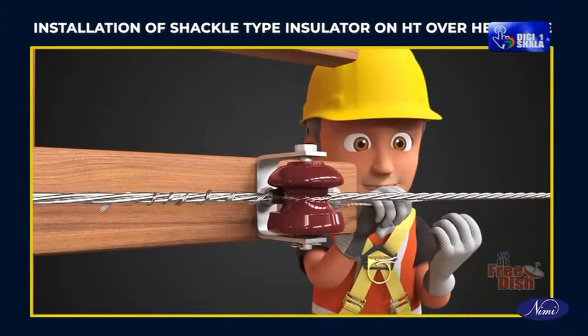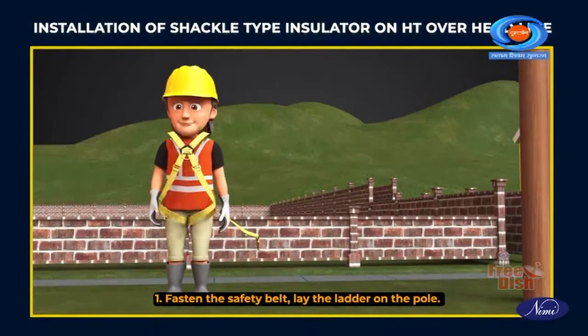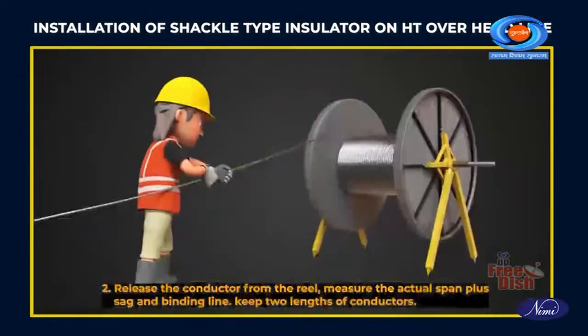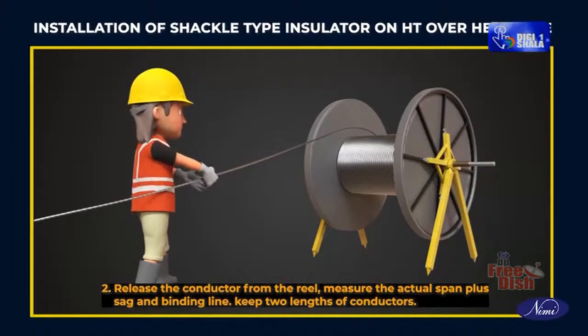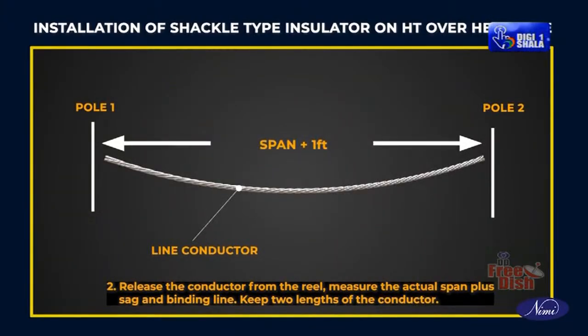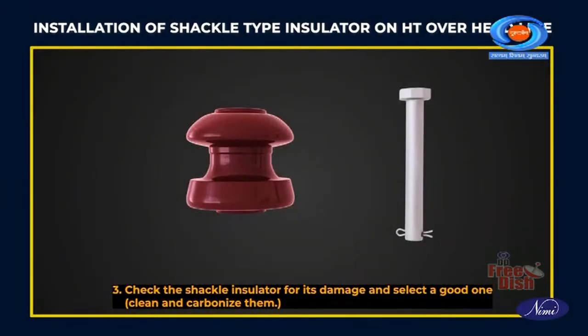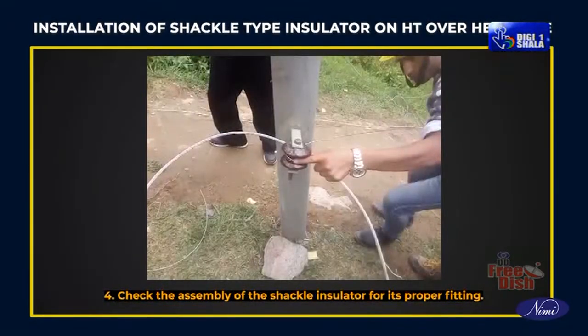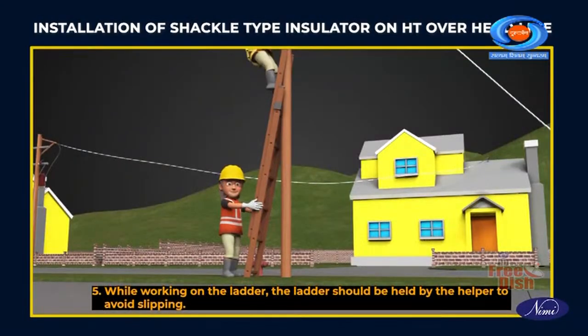Installation of shackle type insulator on HT overhead line. Fasten the safety belt, lay the ladder on the pole. Release the conductor from the reel, measure the actual span plus sag and binding length. Keep 2 lengths of the conductor. Check the shackle insulator for damage and select a good one. Check the assembly of the shackle insulator for its proper fitting. While working, the ladder should be held by the helper to avoid slipping.